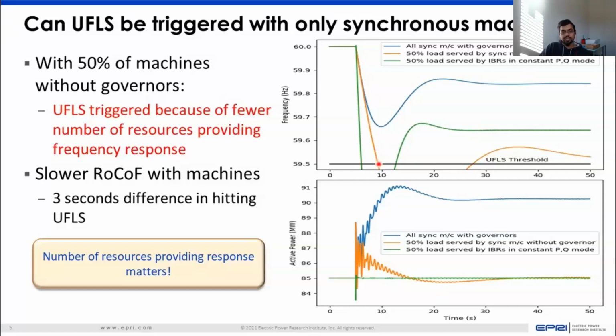So if you have synchronous machines with governors turned off, you gain 3 seconds, as opposed to having the inverter-based resources not providing percentage of the load and not really responding, but at the same time, you still run the risk of hitting UFLS.